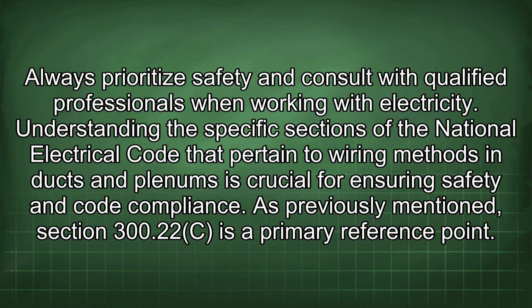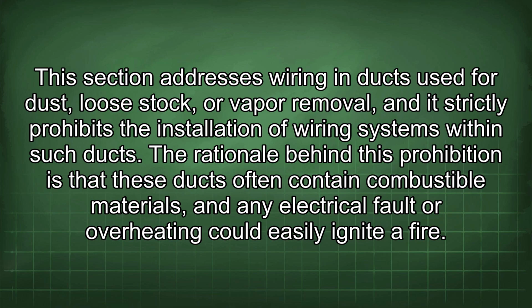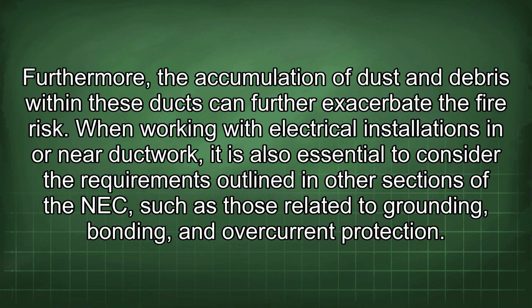Understanding the specific sections of the National Electrical Code that pertain to wiring methods in ducts and plenums is crucial for ensuring safety and code compliance. As previously mentioned, Section 300.22(C) is the primary reference point. This section addresses wiring in ducts used for dust, loose stock, or vapor removal, and it strictly prohibits the installation of wiring systems within such ducts. The rationale behind this prohibition is that these ducts often contain combustible materials, and any electrical fault or overheating could easily ignite a fire. Furthermore, the accumulation of dust and debris within these ducts can further exacerbate the fire risk.